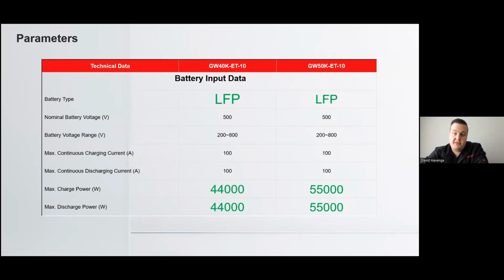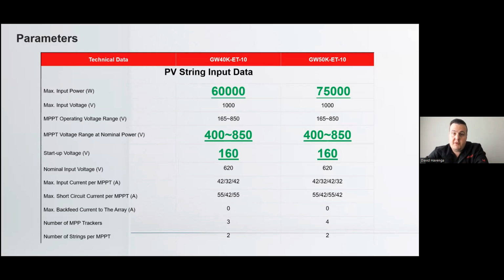You'll see we do support a continuous charge and discharge power of 10% higher than the inverter's rating, so on the 50 kilowatt, 55 kilowatts. And that's both for charging and discharging. Yet again, we also have our 50% oversizing on our DC side. So for all of our hybrid inverters, that is usable DC. You can oversize it and use that DC for both charging and AC at the same time.